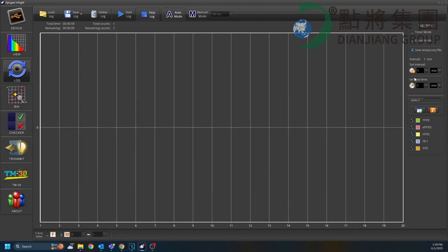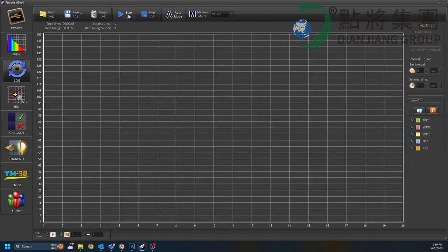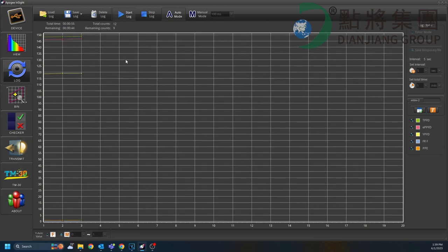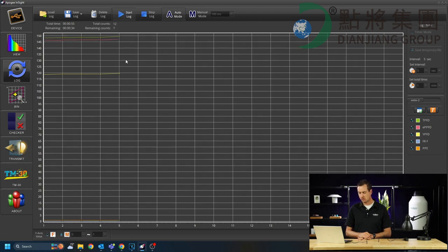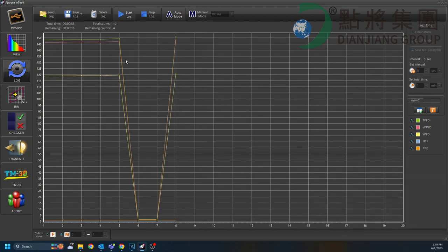Now we're going to go to log mode. In log mode, you can change the different parameters. Over on the right side, you can set the interval, how long between the captures, and for a total time. Or you can do it by how many captures are taken. Let's go change this to seconds, and we'll do one every 5 seconds for a total of 1 minute. Then you can press the Start Log button. It'll begin taking those measurements. You can see they're going to start displaying as they're taken. If you want to stop before the total interval has gone through, press the stop button.